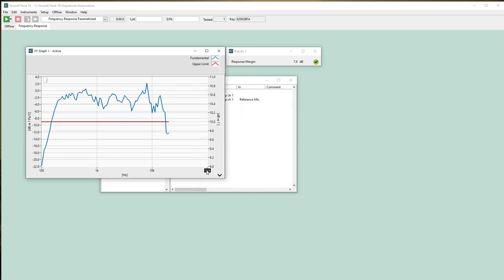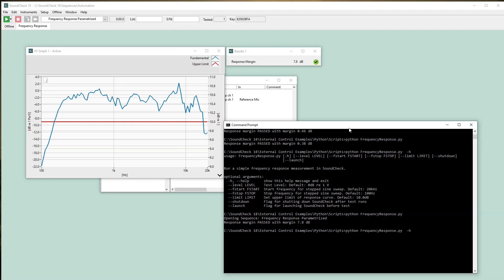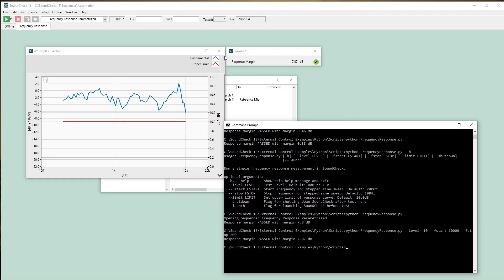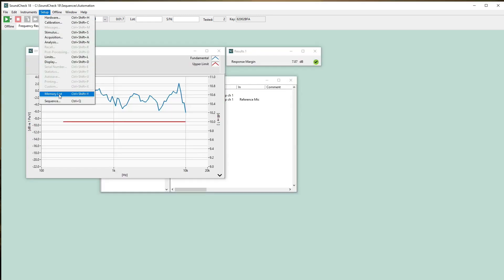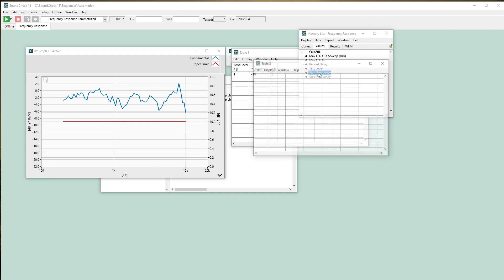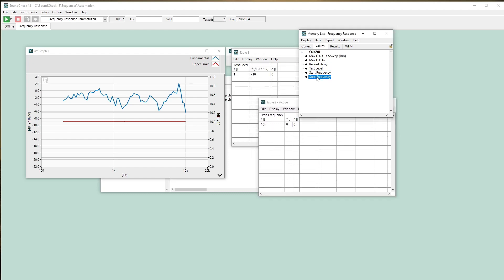I'll change test level, start frequency, and stop frequency, and note how the graph updates and the memory list values take direct input from the script. There are many use cases for this feature. The obvious is that you can maintain a single test sequence and run separate scripts for different models of your device under test. You can also define your own memory list items and perform conditional steps in your test sequence. This is an often requested feature, and we're proud to offer it in Soundcheck 18.